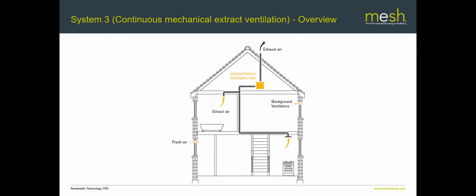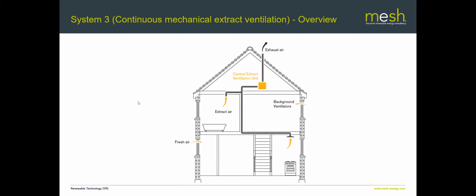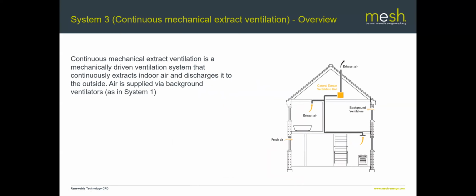System 3 is very similar to system 1. The main difference being that the fans run continuously rather than running intermittently. So that is the continuous mechanical extract ventilation. It's that continuous bit which is the difference. This is possibly the quickest way to move away from system 1: to just put in a central, well, it could be a decentralized fan unit, but a fan unit that runs all the time. You would have a system that goes through the entire house, or you could have individual rooms, but it runs all the time.